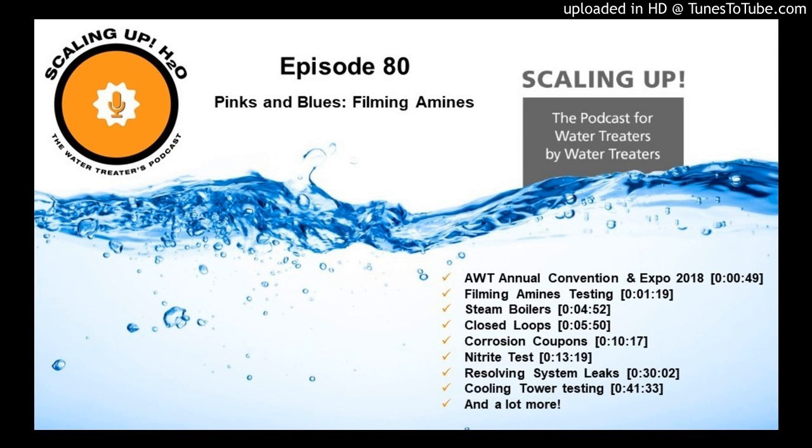And we did get better results, but again, they were just so close that if you didn't have a problem that you were chasing, that your regular product was not able to solve, then that's when we go to this product. Now, I will tell you, we have some extremely high temperature systems that there is no way that we would be able to run without scaling some of the things that are in our other products, and we use Filming Amines there, and we use them very well, and there's data to support that the hotter the surface is, the better the filming amines work.